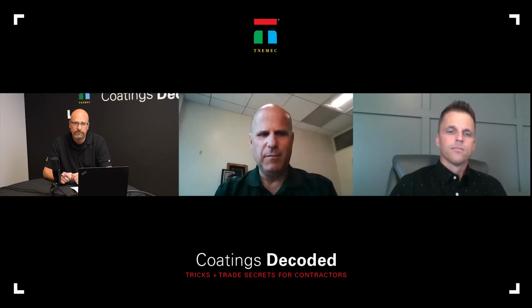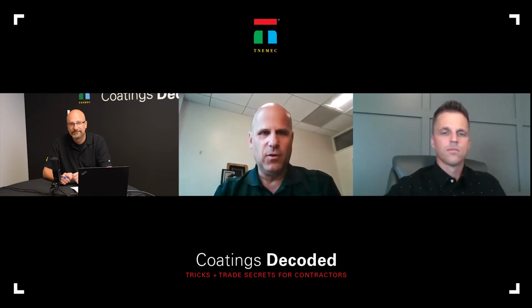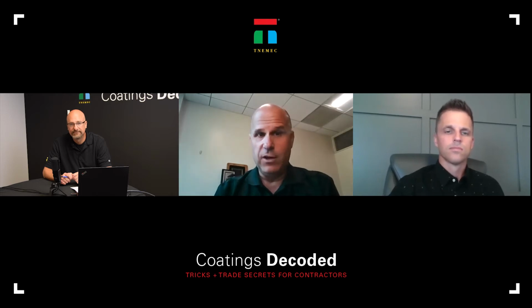Sure. So I'm using K value and thermal conductivity somewhat interchangeably. Thermal conductivity is the more general term, and K value usually is used when you're putting things in the English system. So it's typically measured in BTU inch per hour foot squared degree F, as opposed to watts per meter degree Kelvin. Often when people hear K value or K factor, they're thinking in those English terms. Those are measurable properties, and you can do standard tests to determine the material properties.